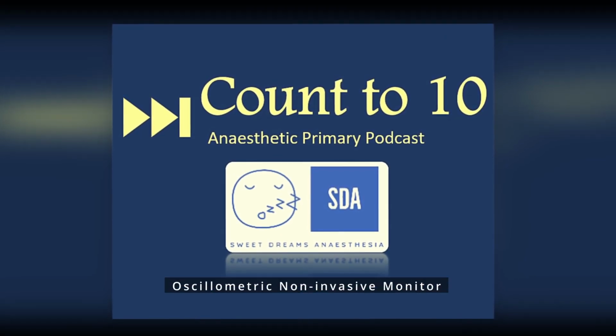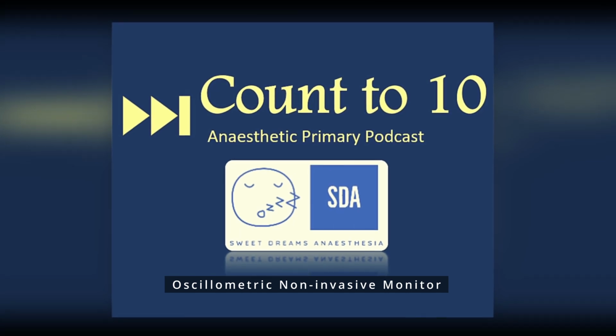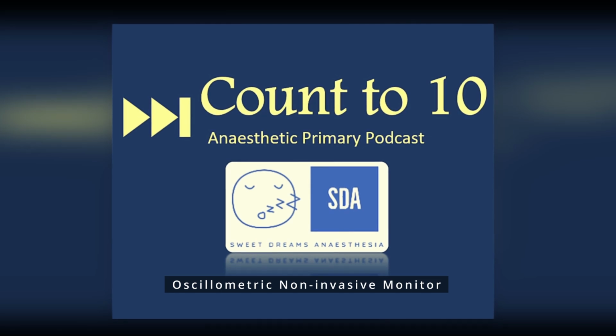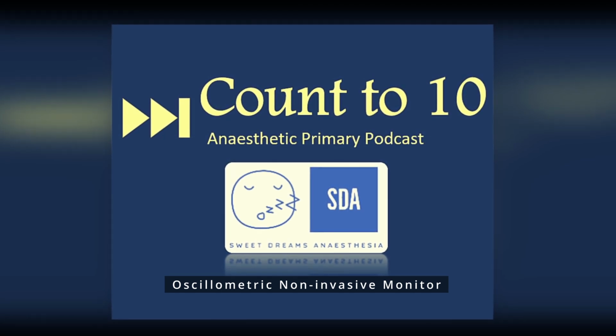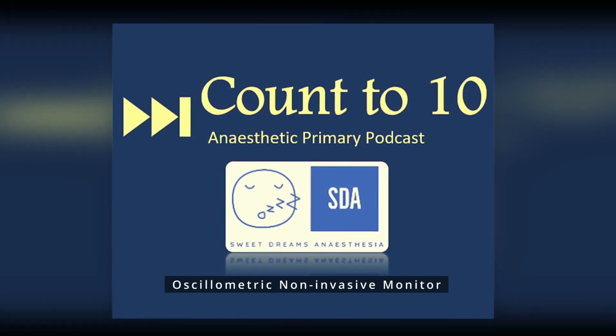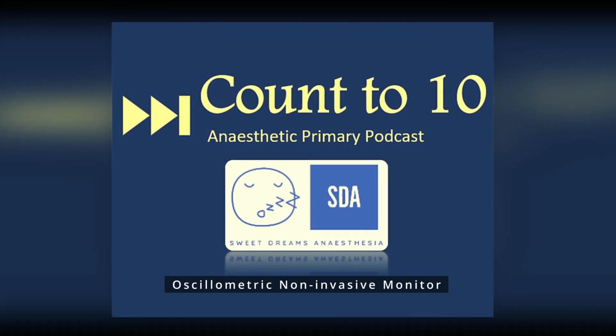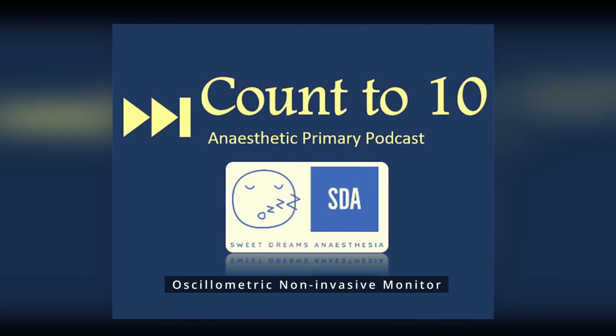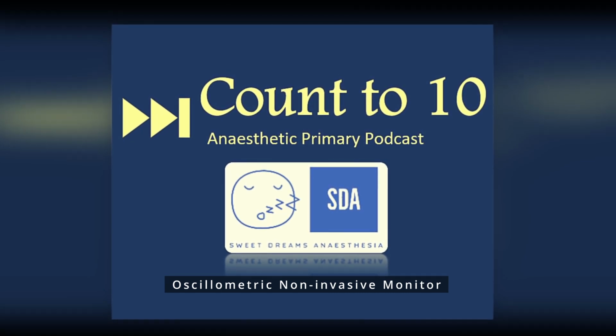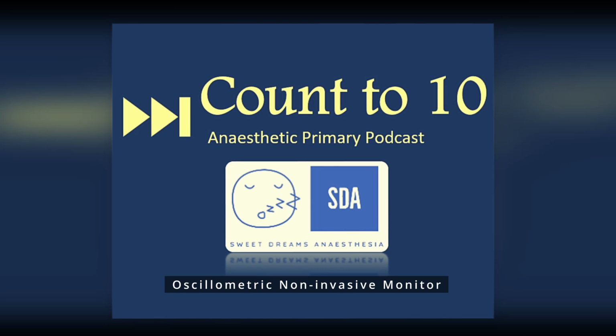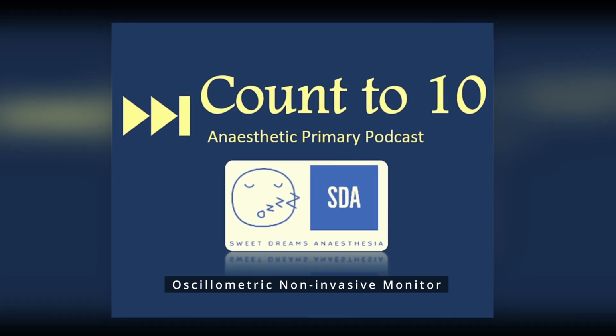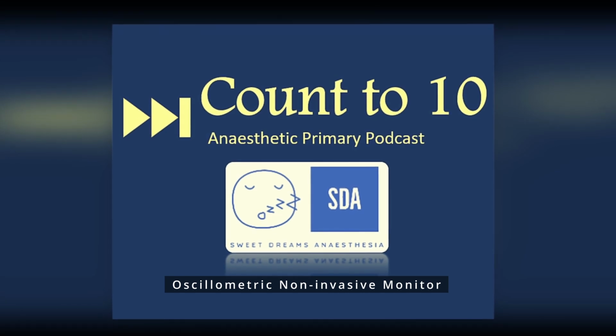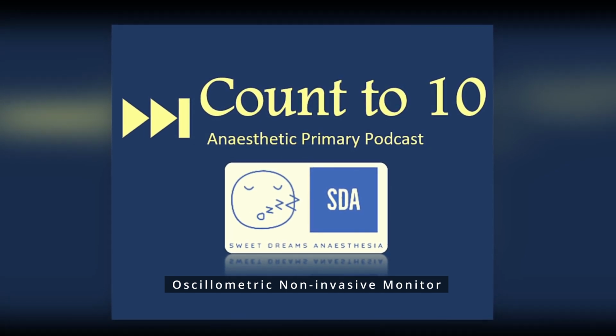The second method of measuring non-invasive blood pressure is a technique called oscillometry. Oscillometry works on the principle that arterial pulsations cause oscillations in cuff pressure, which is then measured by a pressure transducer within the cuff. The key thing to note with this technique is that not all oscillations are the same. Each oscillation has a different amplitude, and we rely on the change in amplitude to help tell us what is systolic, what is mean arterial, and what is diastolic blood pressure.